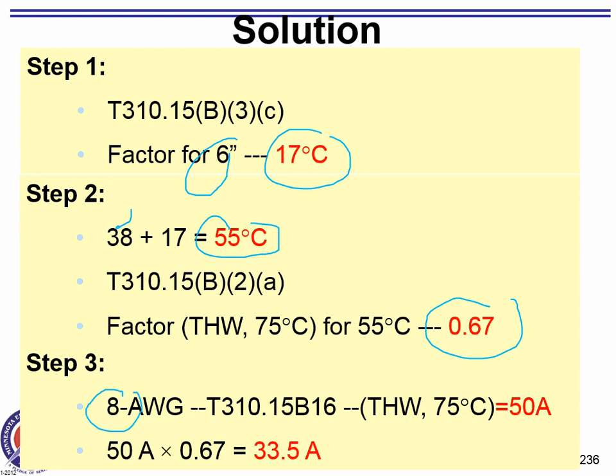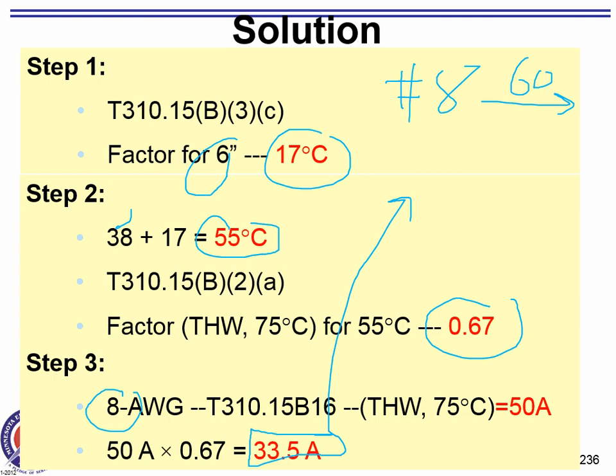Now, under normal operating condition, here's the confusion. Go to find the ampacity of that conductor, and then multiply it by the derating factor, I get 33 point. Now, once you get there, I would like you guys to go to number 8. You need to check number 8 under normal operating condition, which is 60. How much current can you carry? 40 amps. The normal operation of the conductor rules. That's here. And then you do the derating, whatever you come up with, you can't come up with more than what the conductor under normal operating condition can carry.